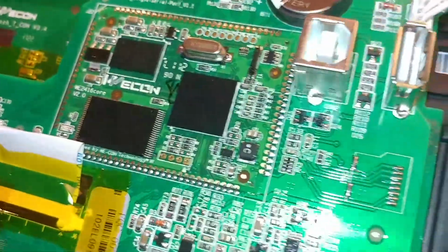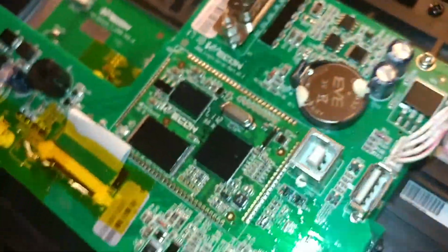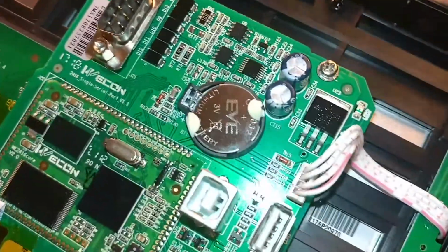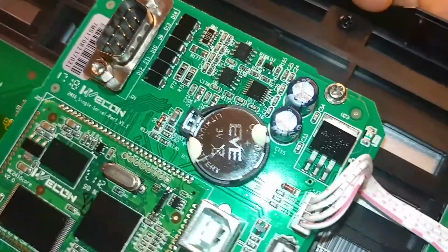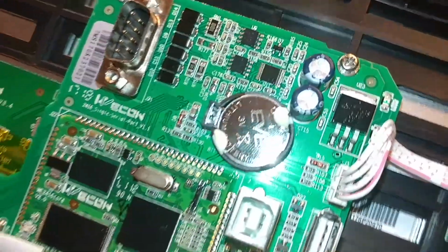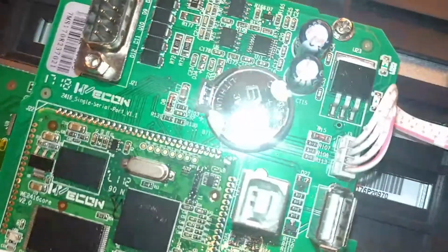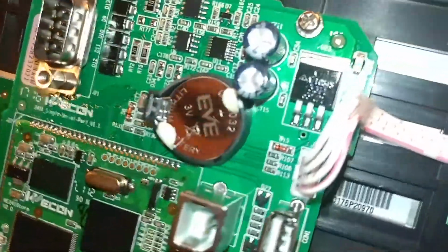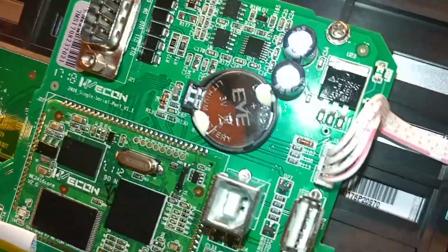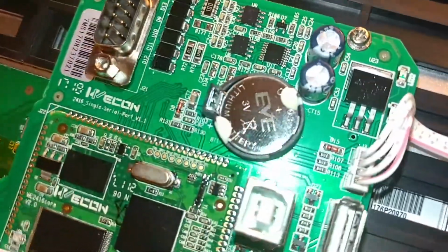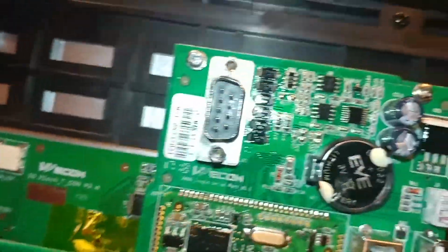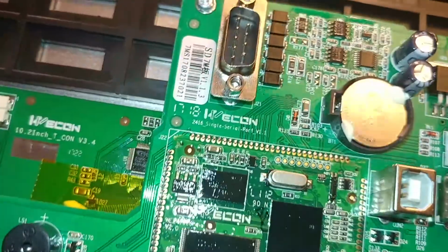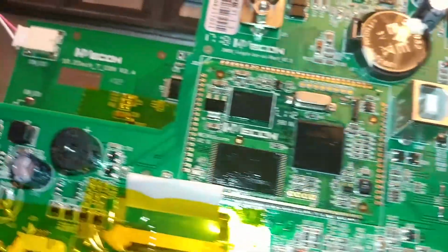The conformal coating is a great addition and will hopefully ensure reliability. You can see here the real-time clock battery has got glue gobs, just like the PLC did, to hold it in. That's a nice feature because it's very unlikely that you'll ever change this battery. It should last the life of the unit. In fact, almost the whole board is conformal coated, so that is a great thing to see. That'll give good protection against moisture.